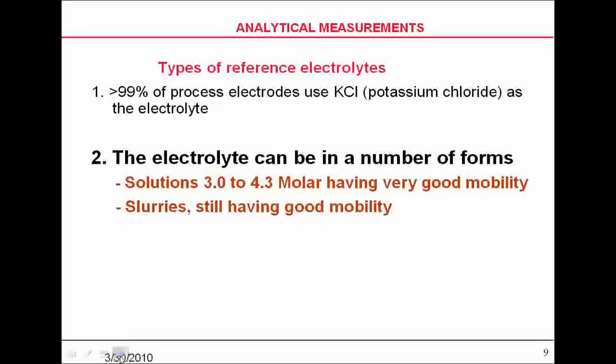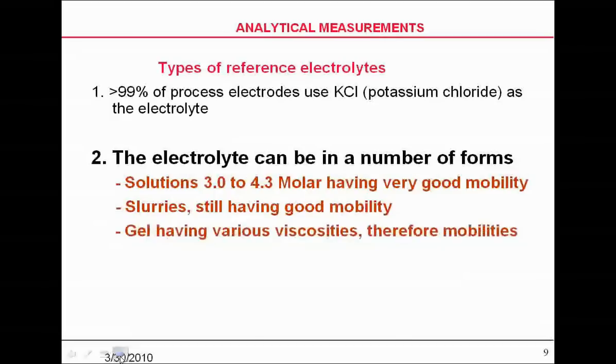You can use a slurry, which also has still good mobility. If you think about potassium chloride or reference solution, what you want it to do is migrate. You want it to migrate out of the reference electrode and into the solution. So you're looking for something that has good mobility.